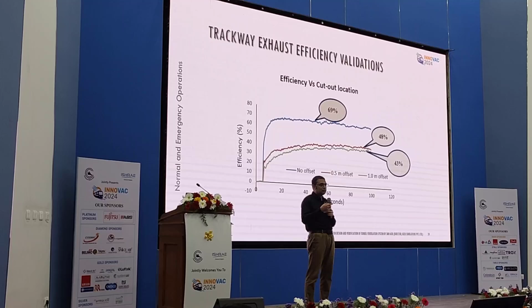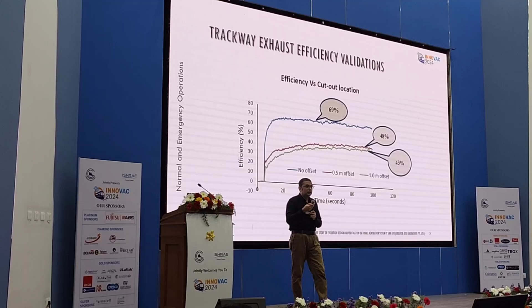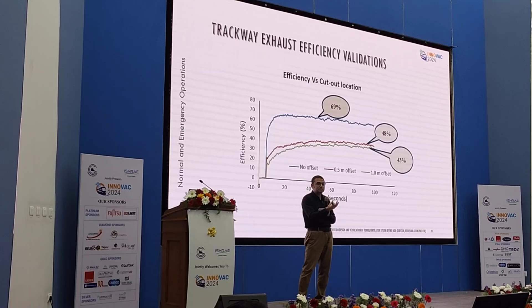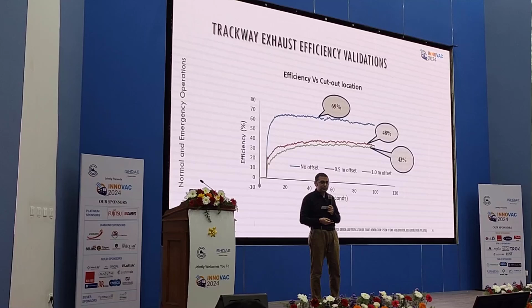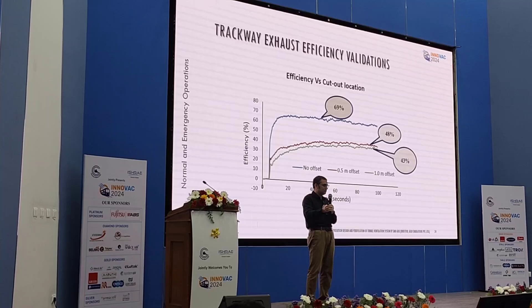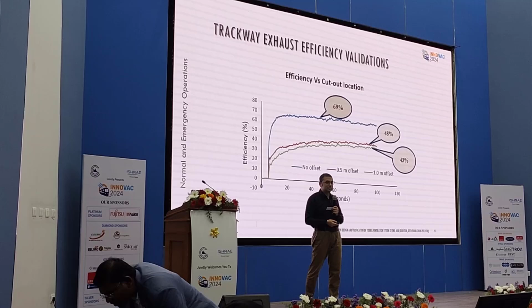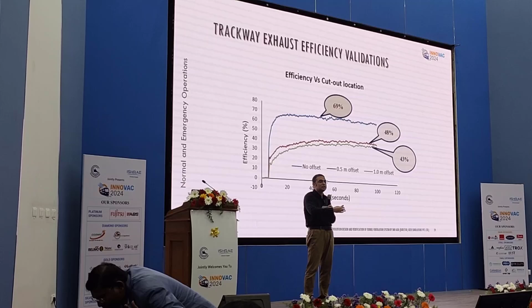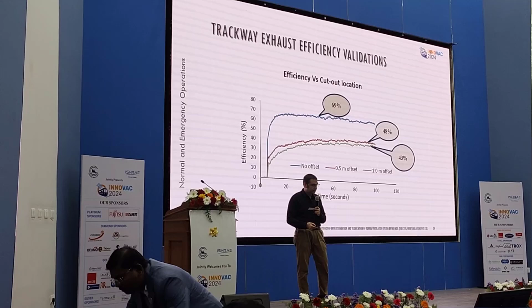Similarly, the trackway exhaust system: just where the train docks at the station, there is a duct on top that takes away the heat. In case that duct's openings are just beneath the condenser it's designed for, it takes away almost 70% of the heat. In case the train stops slightly offset from that specific position, you get 48% or 43% heat rejection. So this is something we account for, and this is how we interface with the signaling system to determine where to stop the train and where not to.